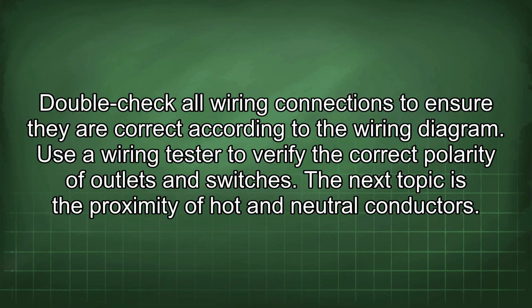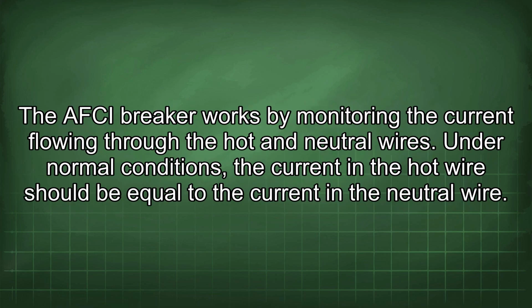The next topic is the proximity of hot and neutral conductors. The AFCI breaker works by monitoring the current flowing through the hot and neutral wires. Under normal conditions, the current in the hot wire should be equal to the current in the neutral wire.